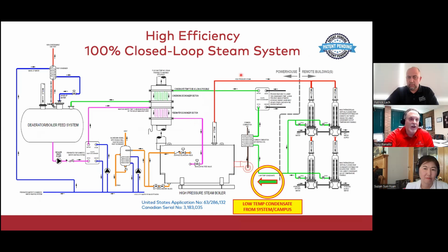Now you see that little gray line right here, right? We're delineating powerhouse versus remote buildings on a campus or maybe in a complex. Could just be a remote room in the same building if the powerhouse happens to be somewhere in the same building. The whole concept here is that we only have steam going out and we have condensate coming back. Everything we need to do to have high efficiency, though, is by the boiler. We don't have access to the hydronic system for these particular heat exchangers. These could be heat exchangers for building heat, for domestic hot water, or some other process. Manufacturing could even use them for processes. As long as we can get this low temperature condensate back, we can do something with it.